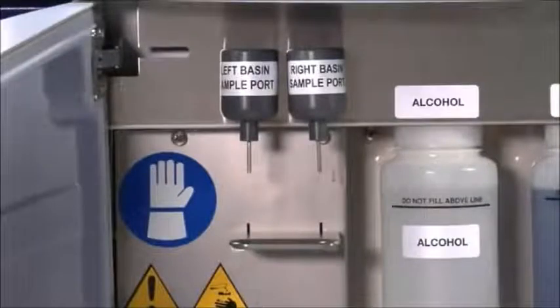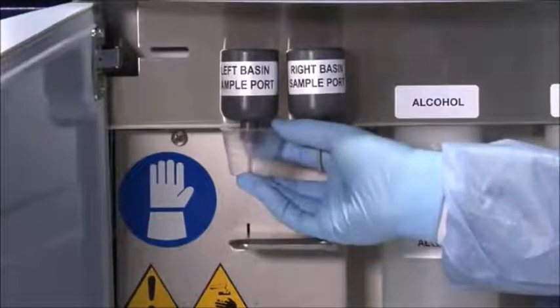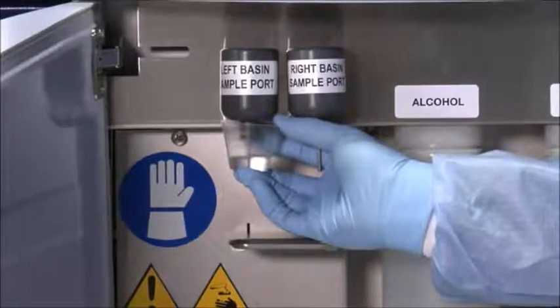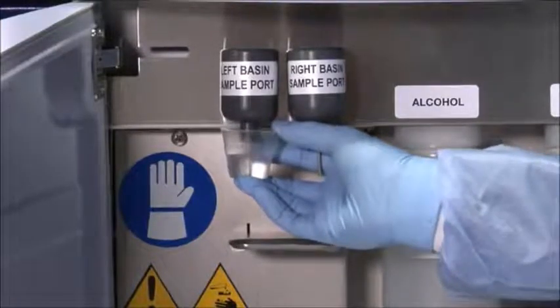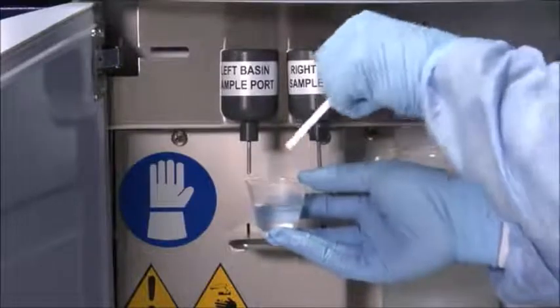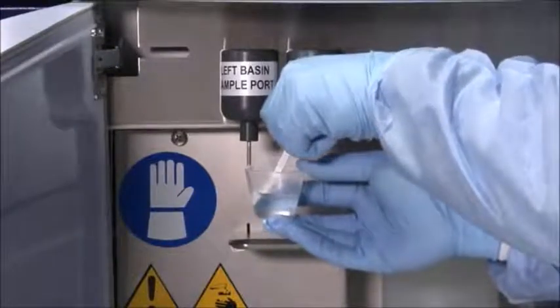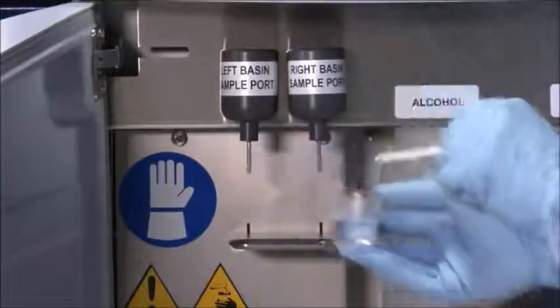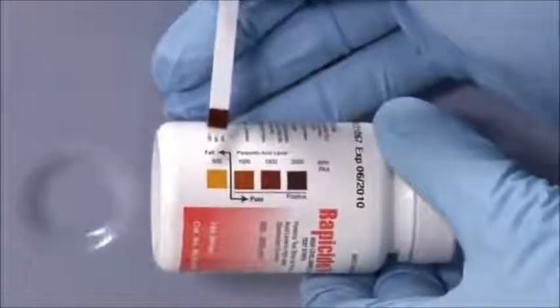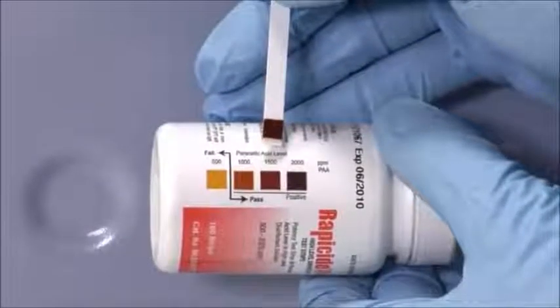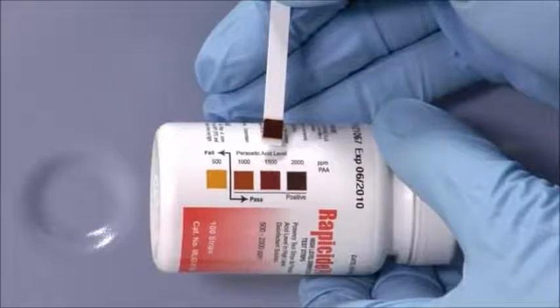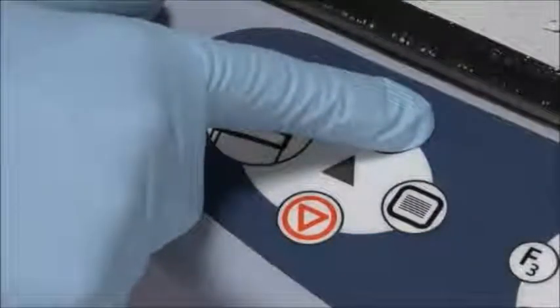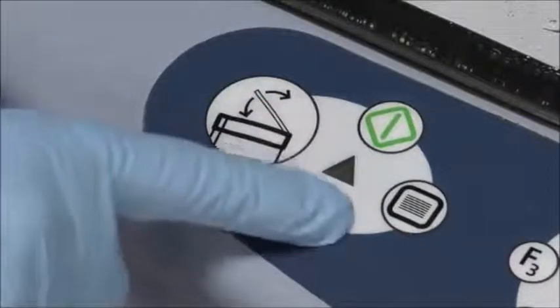Open the front access door and take a sample of disinfectant from the sample port. This is done by pressing a sample cup up against the metal prong. Fluid will be dispensed into the cup. Put the indicator portion of the Rapicide PA test strip into the disinfectant for 1 second and remove. Wait 30 seconds for a reading and compare to the chart on the Rapicide PA test strip bottle. If disinfectant is above the 1,000 part per million, the minimum effective concentration, or MEC, has passed. Indicate a pass by pressing the Start button or a fail by pressing the Cancel button.